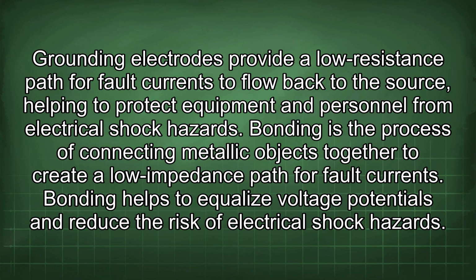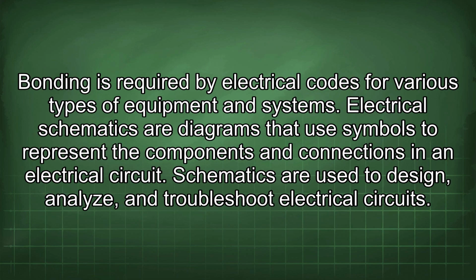Bonding is the process of connecting metallic objects together to create a low impedance path for fault currents. Bonding helps to equalize voltage potentials and reduce the risk of electrical shock hazards. Bonding is required by electrical codes for various types of equipment and systems.